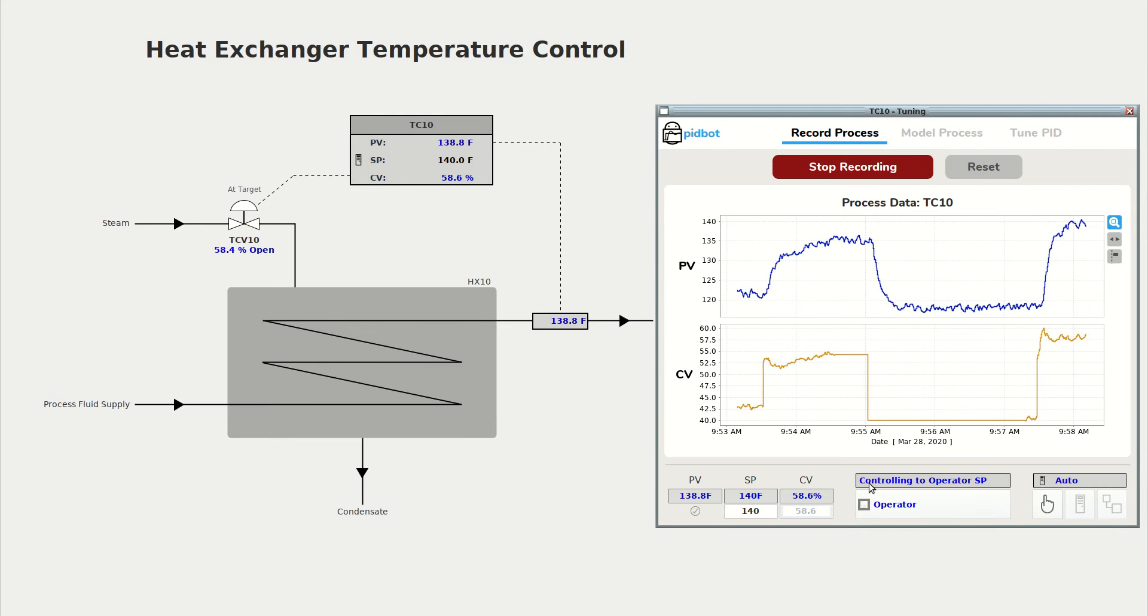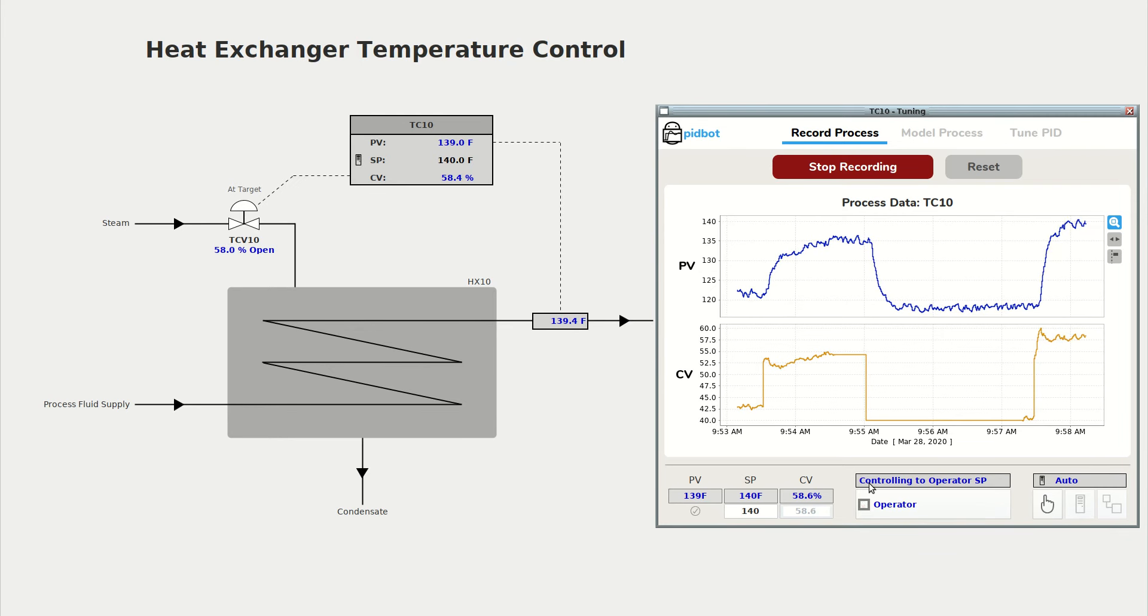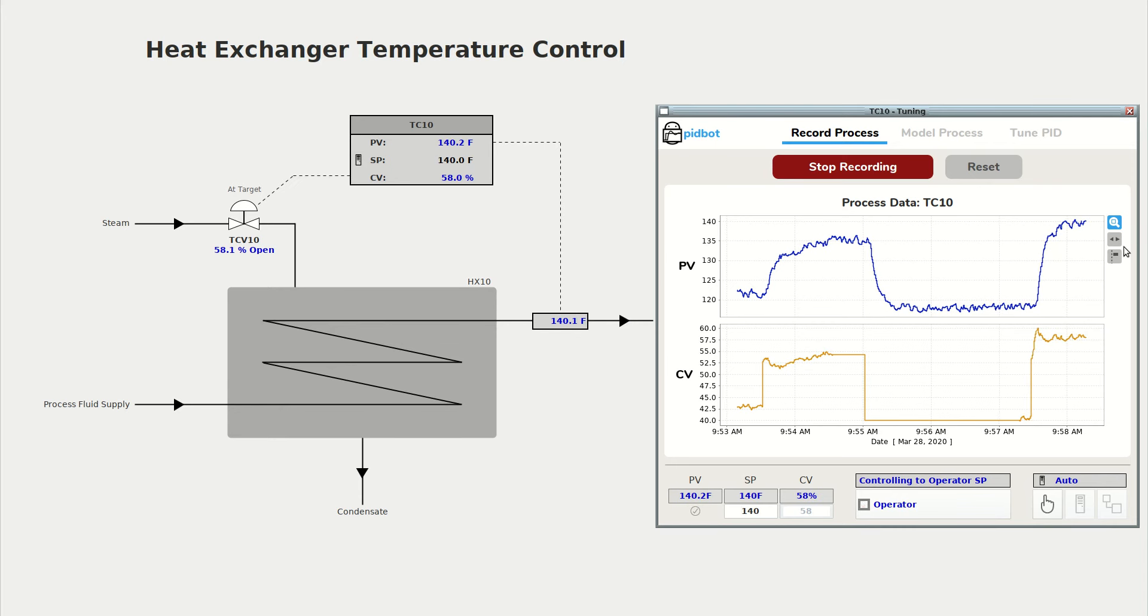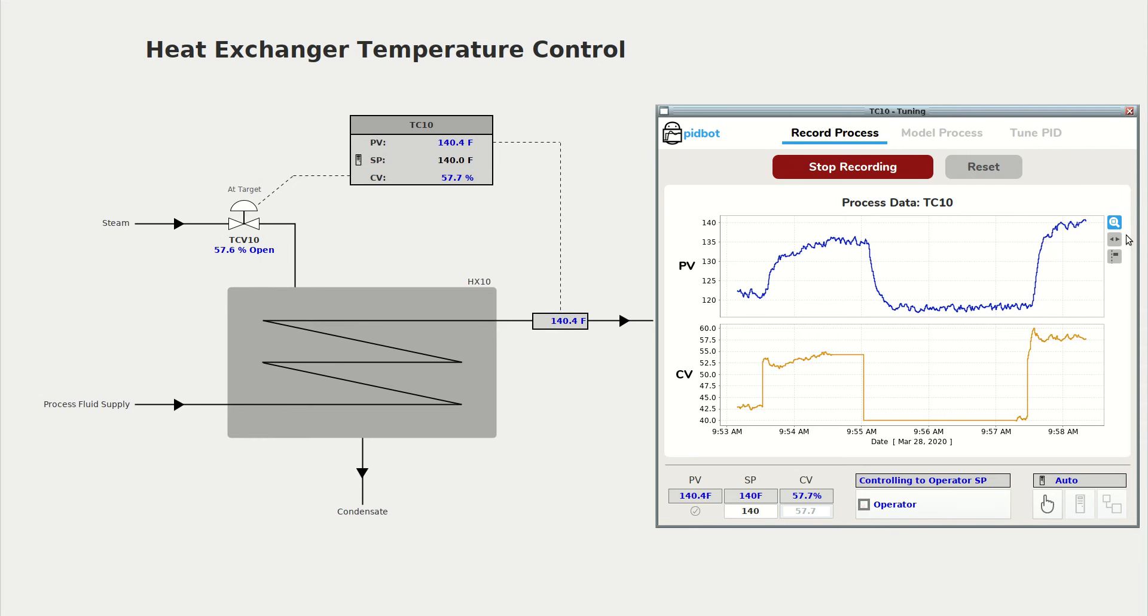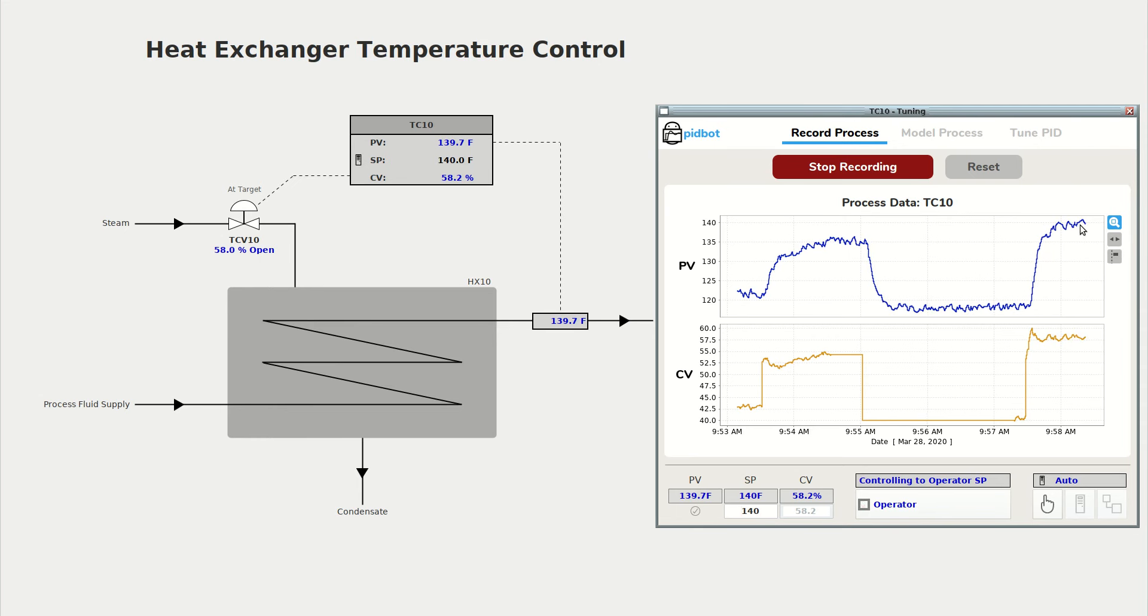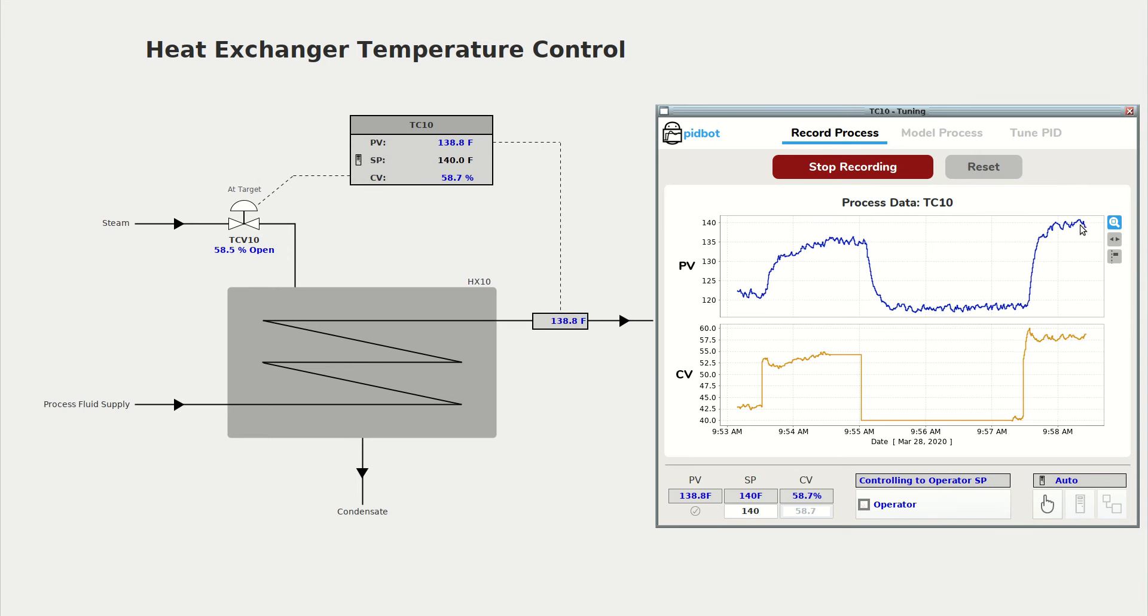That looks good. We've come right up to 140 degrees, our new set point with minimal overshoot, and now it's steadying out to control right at 140, so you can definitely use automatic data to tune with PidBot.